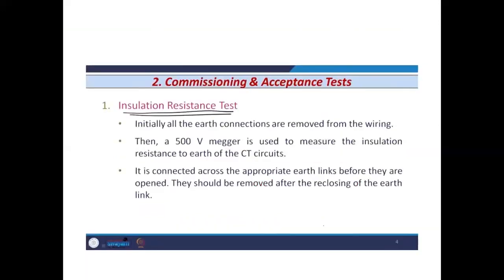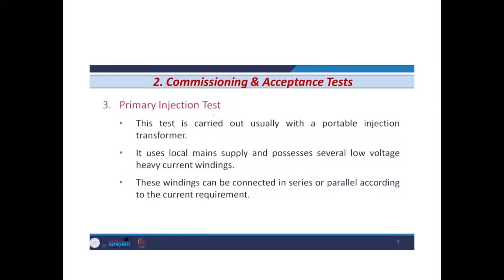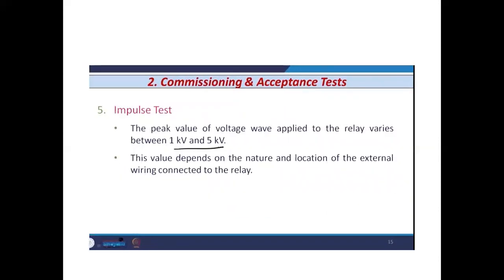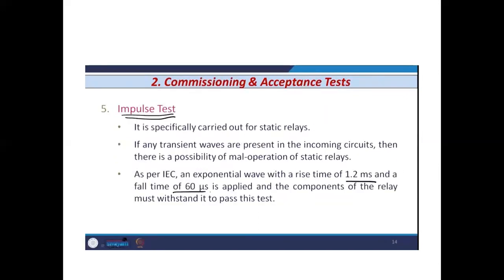Okay, so a proper insulation test, a proper secondary injection and primary injection test, and the tripping test should be performed. And the impulse test is very important because the protective equipment is exposed in the switchyard, in the open air, in the outdoor environment, so there is a chance of lightning. This lightning is actually called the impulse voltage, and an impulse test is to be performed. For that purpose, if the rise time is 1.2 microsecond and the wave tail time is 50 microsecond, then this test is passed. Otherwise, if they are not meeting these requirements, this test has failed.